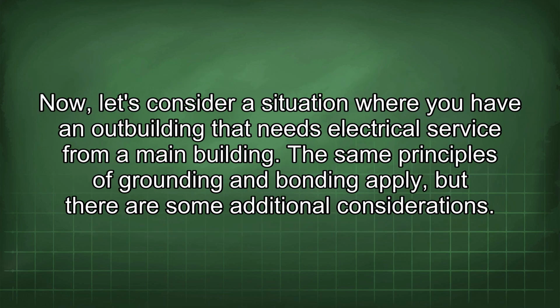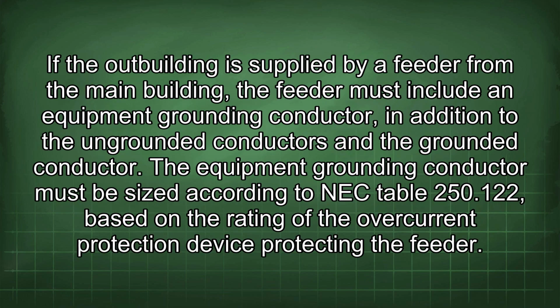Now let's consider a situation where you have an outbuilding that needs electrical service from a main building. The same principles of grounding and bonding apply, but there are some additional considerations. If the outbuilding is supplied by feeder from the main building, the feeder must include an equipment grounding conductor, in addition to the ungrounded conductors and the grounded conductor. The equipment grounding conductor must be sized according to NEC Table 250.122, based on the rating of the overcurrent protection device protecting the feeder.